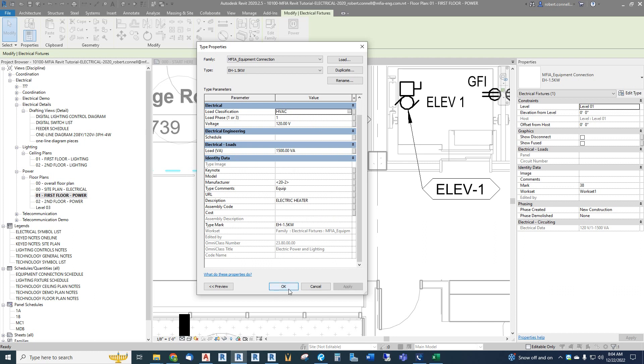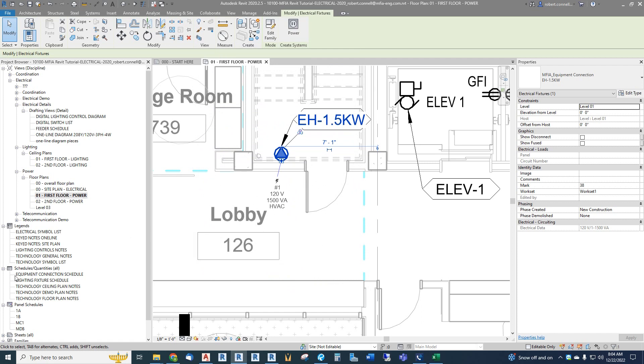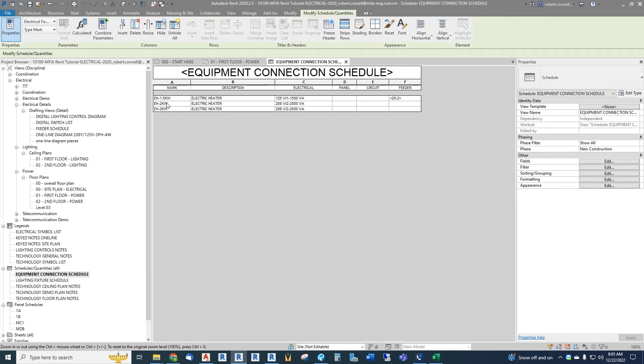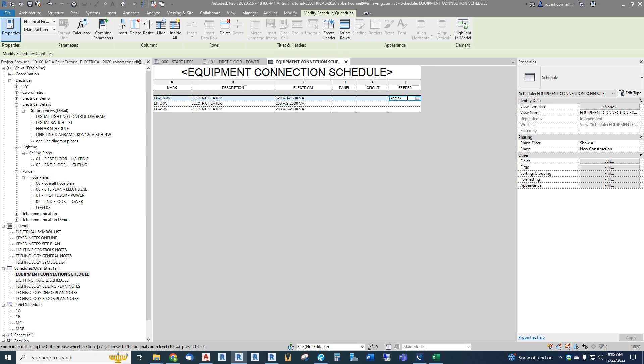Let's look at the equipment schedule — under 'Schedules and Quantities' on the left we have the equipment connection schedule, also known as the mechanical equipment schedule. We can see all our different heaters. The 2 kW appears twice because we inserted it twice in our model, and each one will have different panel and circuit information. We have a description, electrical data pulled in, and the feeder is typed in as text to show wire size, relating to the feeder schedule. This is more like a branch circuit.